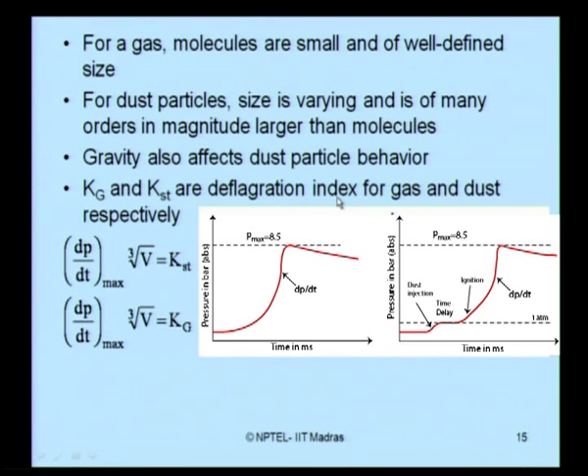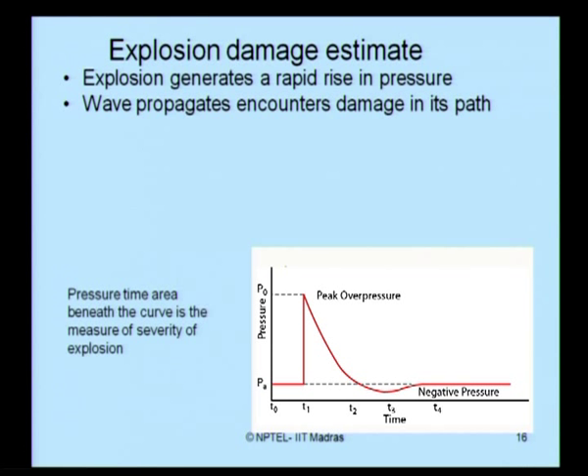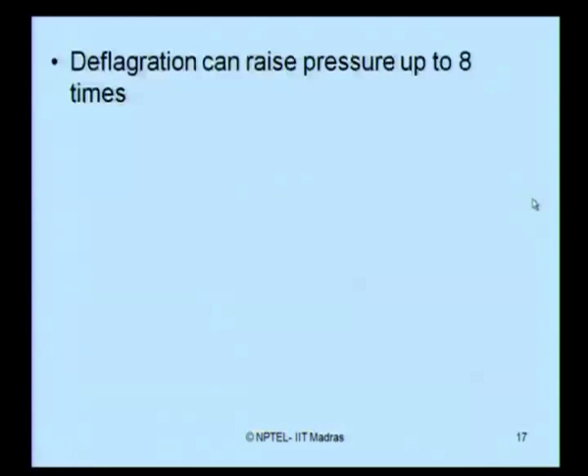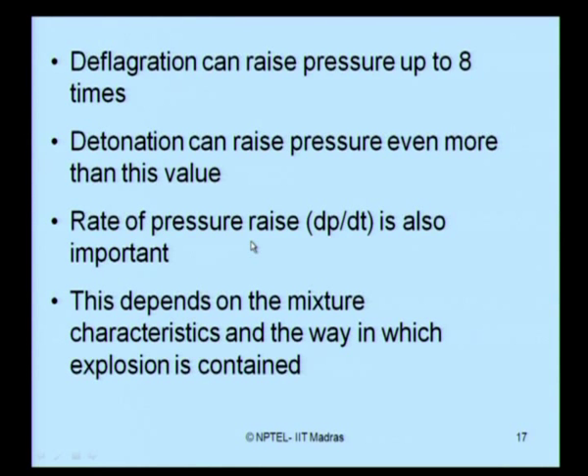Looking at explosion damage estimates, the explosion causes a rapid pressure rise, the wave propagates and encounters damage in its path, followed by a negative pressure phase. The area under this curve gives the measure of severity. Deflagration can raise pressure up to 8 times its value, whereas detonation can raise pressure even more. The rate of pressure rise dp/dt is important to estimate damage caused by dust or gas. The pressure rise depends on the mixture characteristics and the way the explosion is contained.